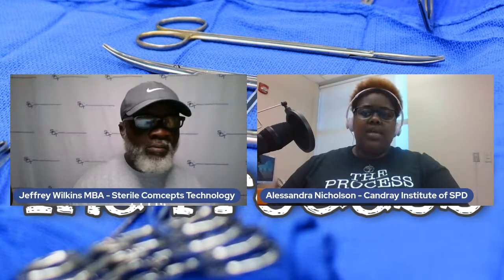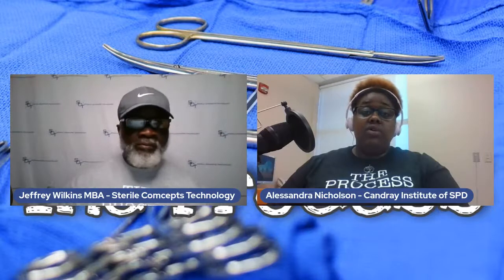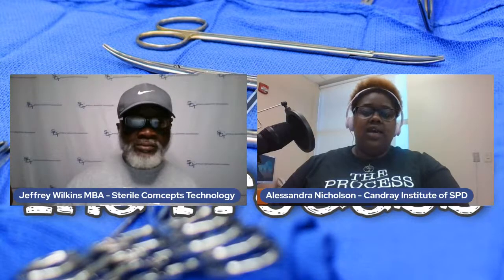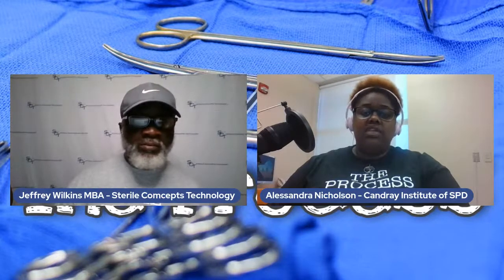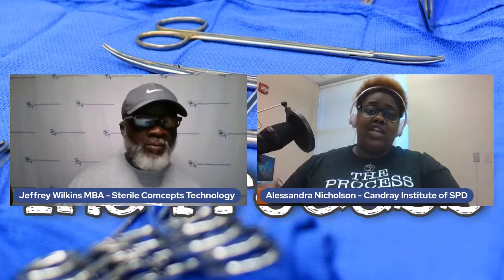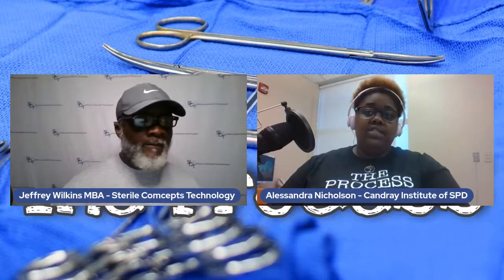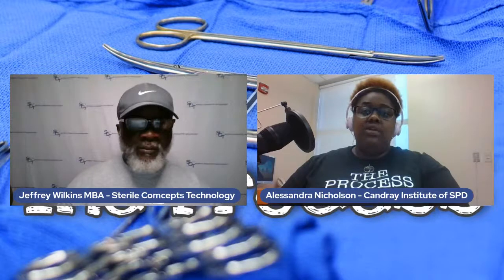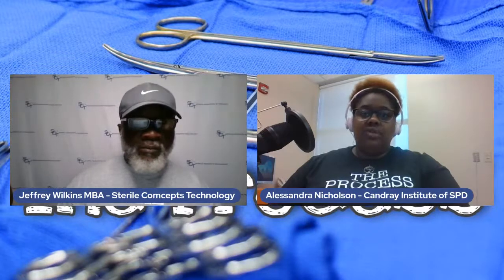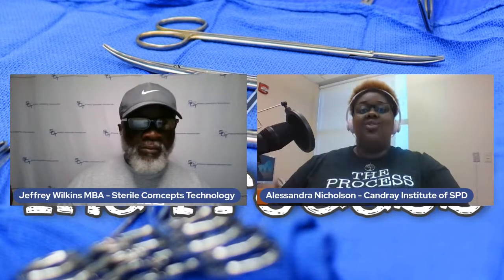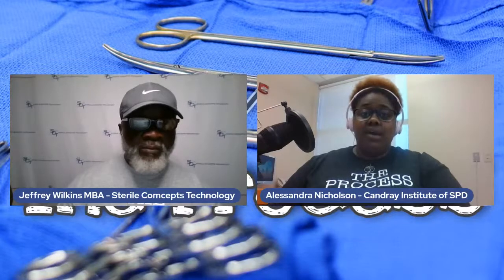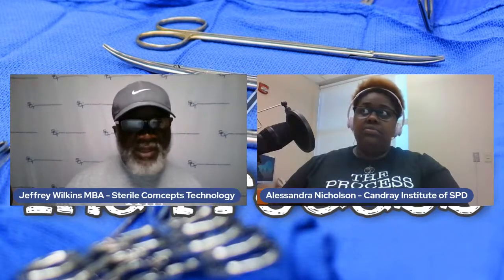So a lot of times I'm seeing, okay, maybe it's a 4 minute exposure, but it says no more than 18. And maybe my hospital is set up for a 10-minute exposure. So that means I don't have to change anything about the way that I'm processing. But do read through those IFUs not just for the information that you're looking for, but so that you are aware of everything that company is saying that they need for that piece of equipment. Yeah, it really makes a difference.